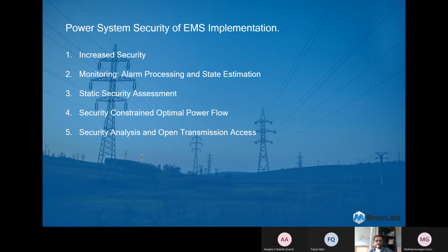In the case of a transmission system, a real-time mathematical model of the power system can be built using a power flow model and a state estimation algorithm, which can read many redundant measurements and calculate statistically, and show the output with more precision. So this is known as state estimation.